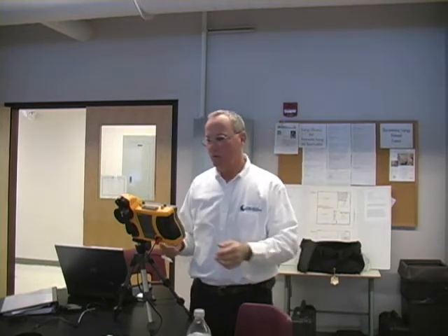You also take images of the house from the inside and the outside. You want to do it on both sides. A blower door is a great way to do that. You put the blower door on, it forces air into or out of the building, and you can get better pictures. If you look at that window, for example, and it's hot from the outside, what does it look like from the inside? If it's cold from the inside and hot from the outside, it's got to be reflected somewhere. It should be the same temperature. You always do it from both sides.